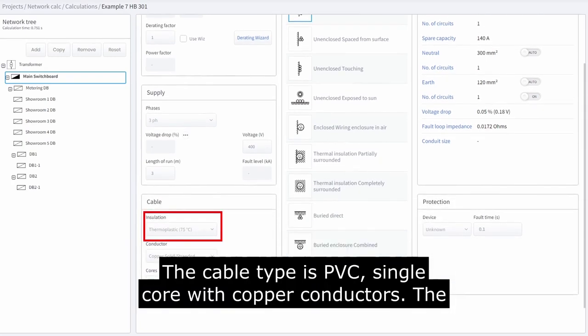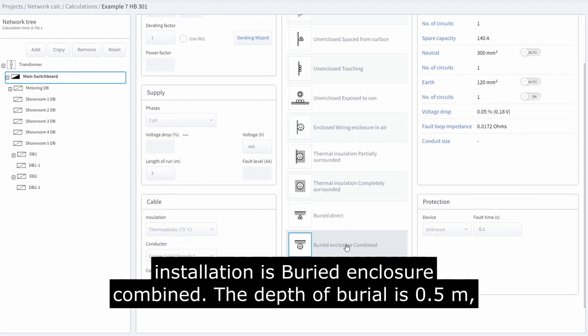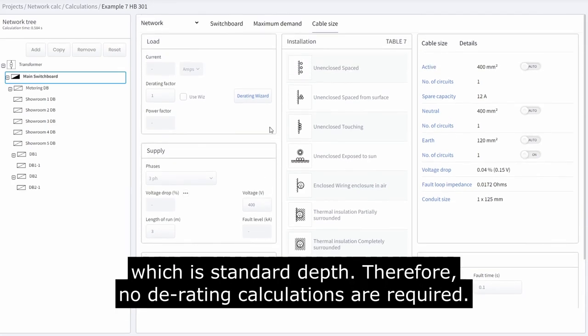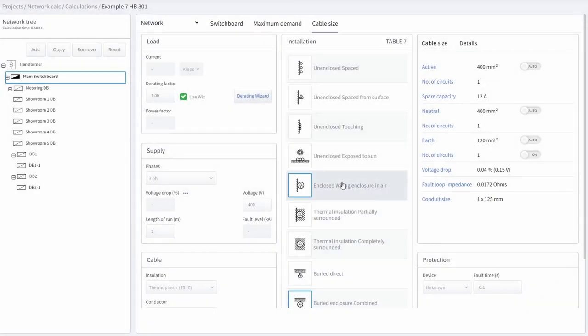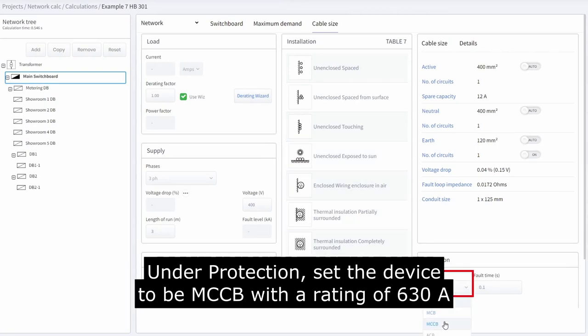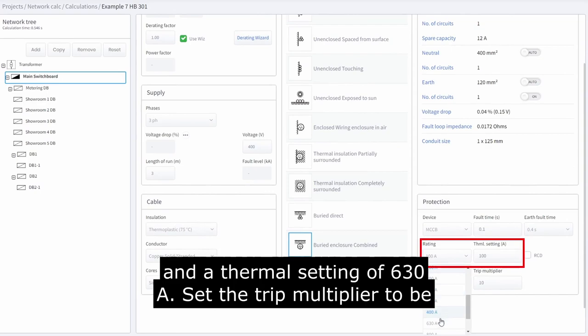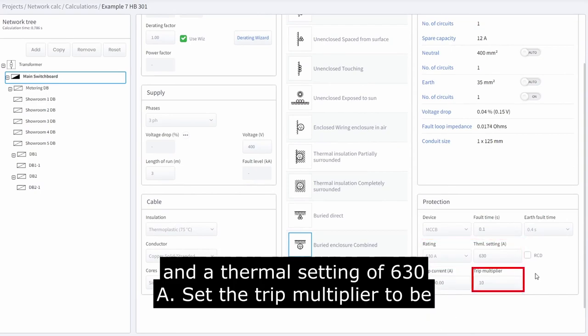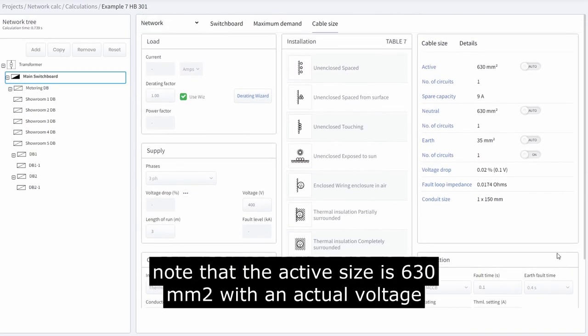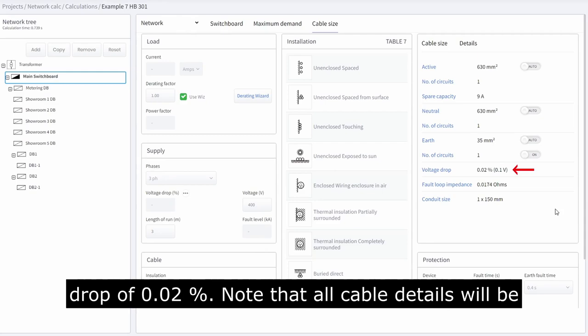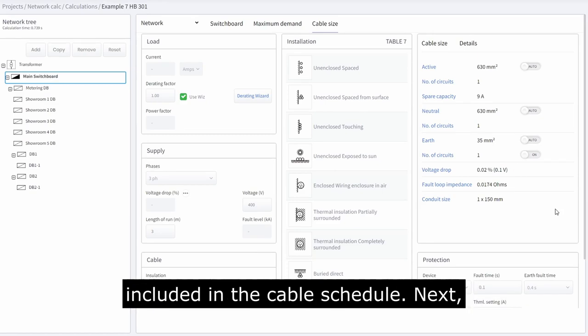The cable type is PVC, single core, with copper conductors. The installation is buried enclosure combined. The depth of burial is 0.5 meters, which is standard depth, therefore no derating calculations are required. Under protection, set the device to be MCCB with a rating of 630 amps and a thermal setting of 630 amps. Set the trip multiplier to 7.5. Under cable size, note that the active size is 630 mm² with an actual voltage drop of 0.02%. All cable details will be included in the cable schedule.